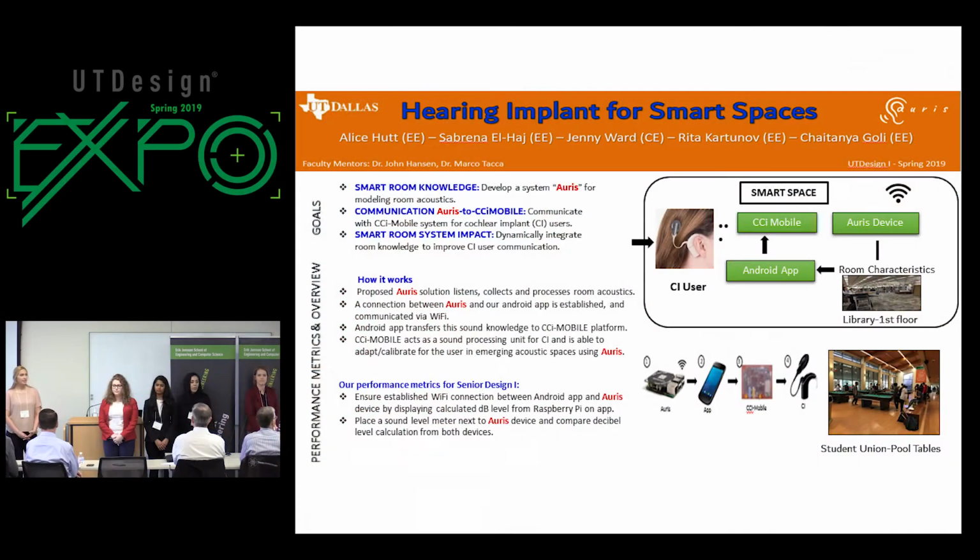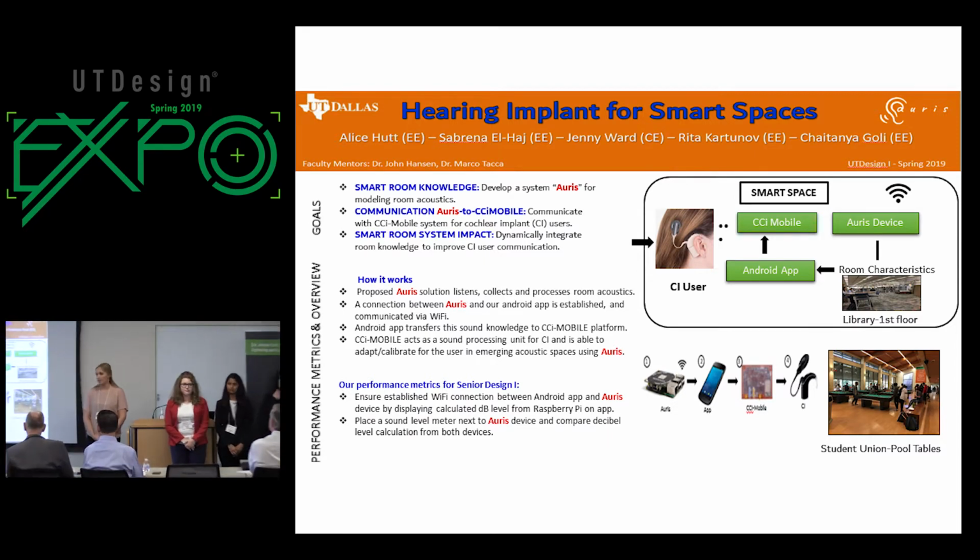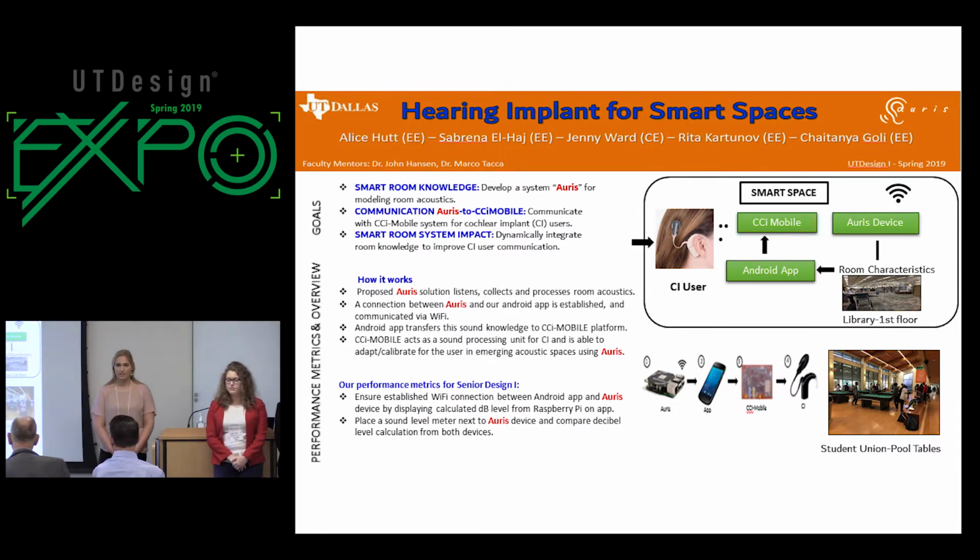A cochlear implant is a device for those who suffer from total hearing loss. There is a sound processor worn behind the ear which captures sound, then processes it into digital code. The processor then transmits this code through the coil on the outside of the patient's head to the implant. The implant then converts the digital code into electric impulses which get sent along the electrode array in the cochlea. Finally, the electrodes stimulate the hearing nerves which send impulses to the brain which get interpreted as sound.